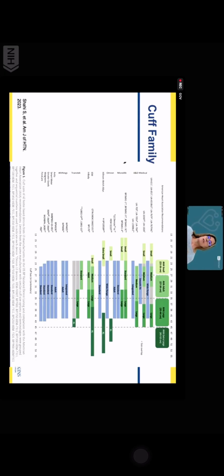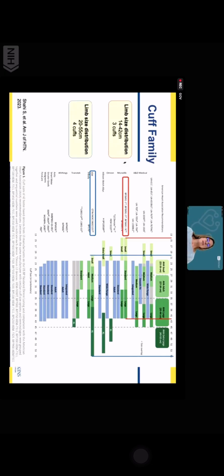So to go through what I was describing earlier in terms of the number tested per cuff and testing across the cuff range, I'm going to use two examples. So we're going to use this example here. You can see that this device comes with 3 different cuffs, and that the cuffs have a limb size distribution of 14 to 42 centimeters, and they achieve that distribution using 3 different cuffs. Now this device comes with 4 different cuffs, and these 4 different cuffs accommodate a different limb size distribution. It accommodates people who have an arm circumference anywhere between 20 and 55 centimeters. Next slide.